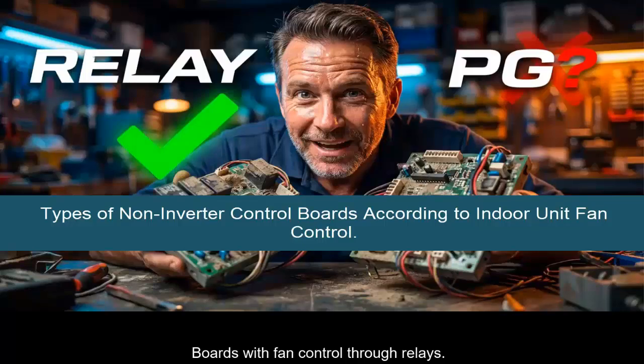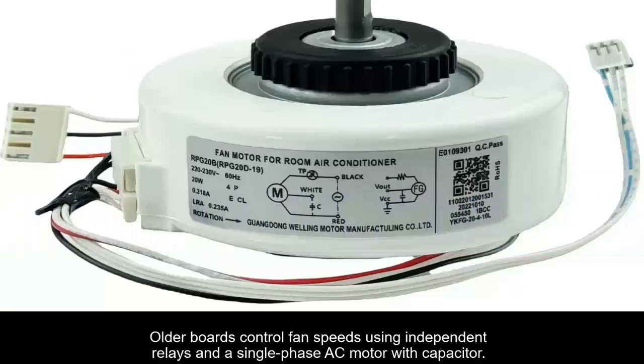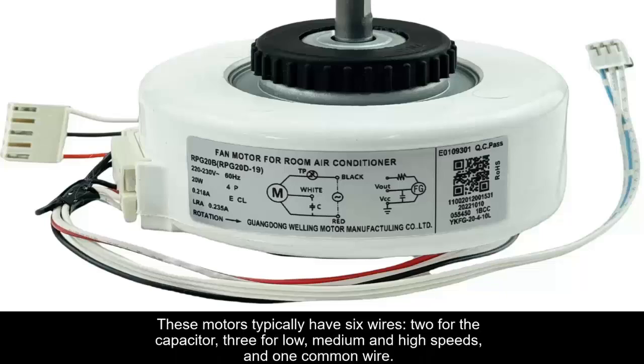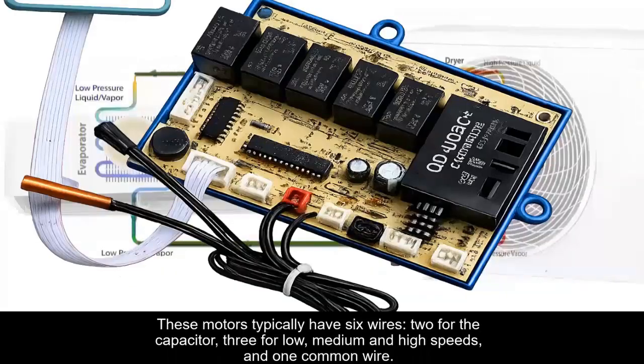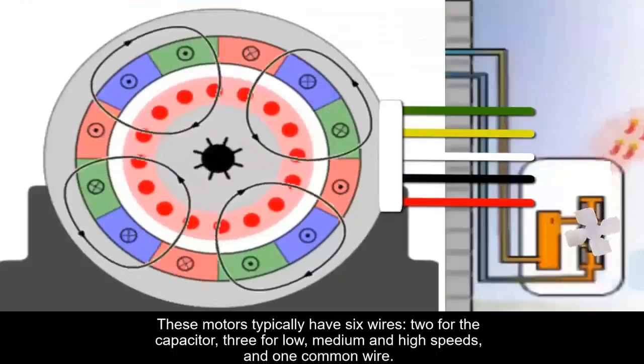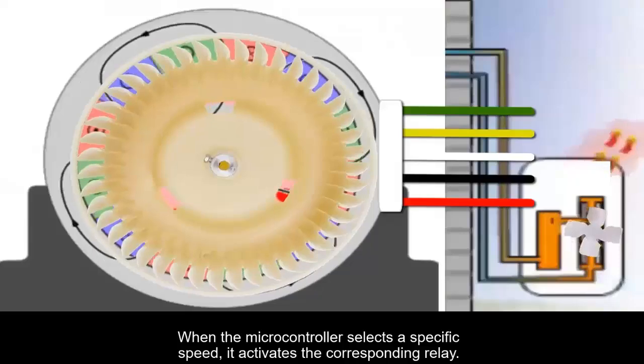Older boards control fan speeds using independent relays. In this system, a single-phase AC motor with permanent capacitor is normally used. These motors typically have 6 wires of the same gauge, 2 wires for the capacitor, 3 wires corresponding to low, medium, and high speeds, and 1 common wire.